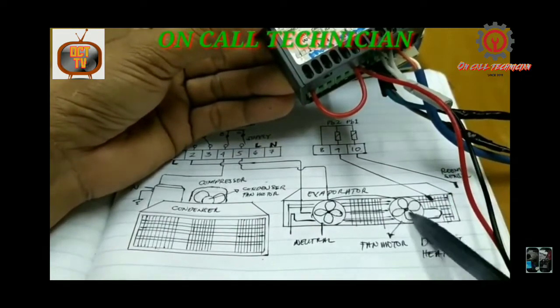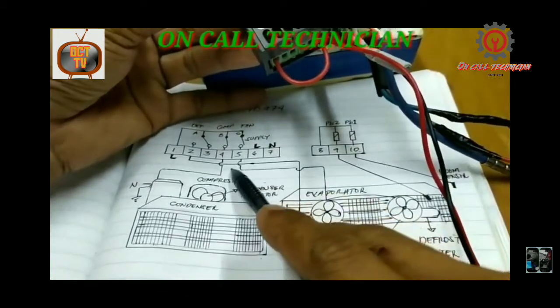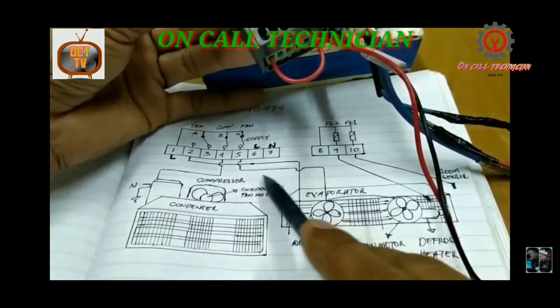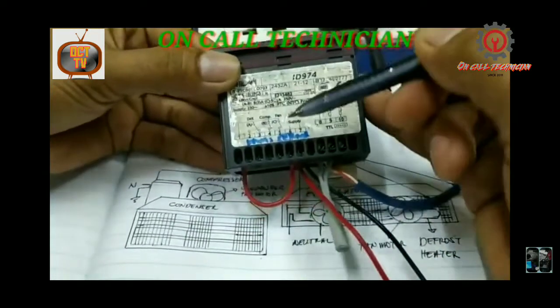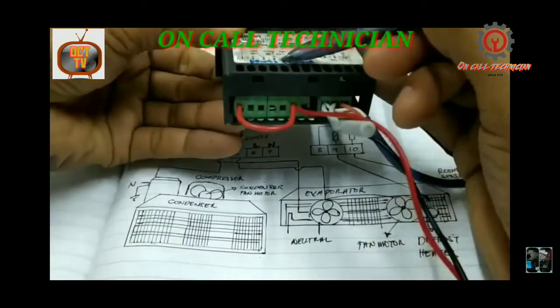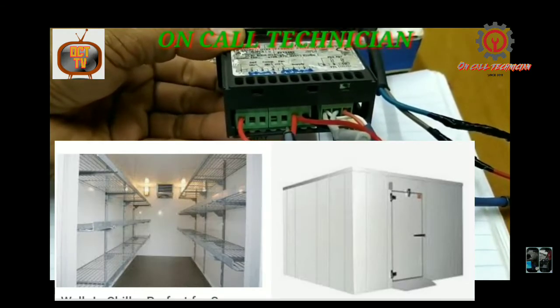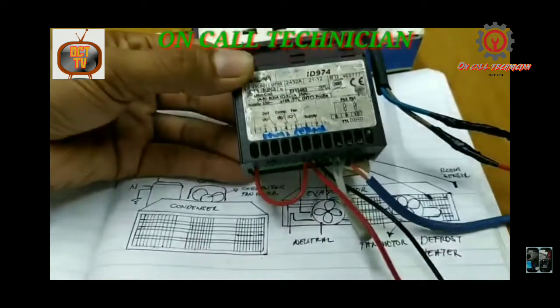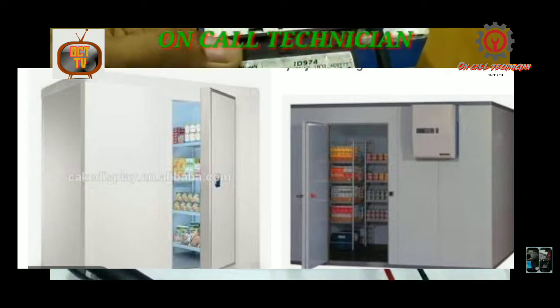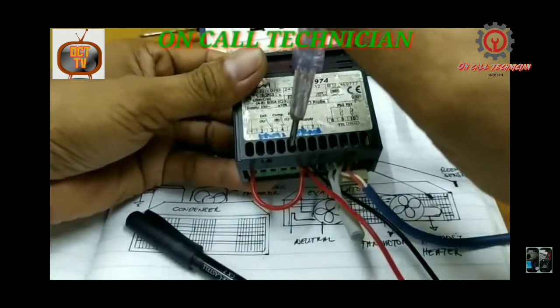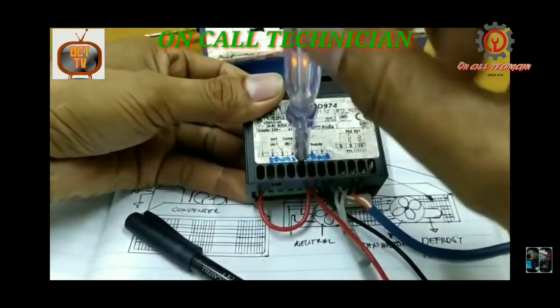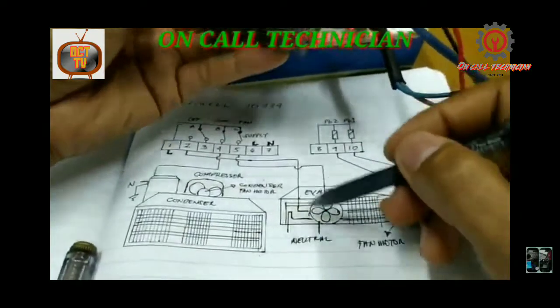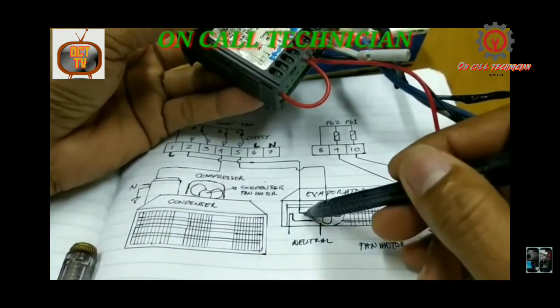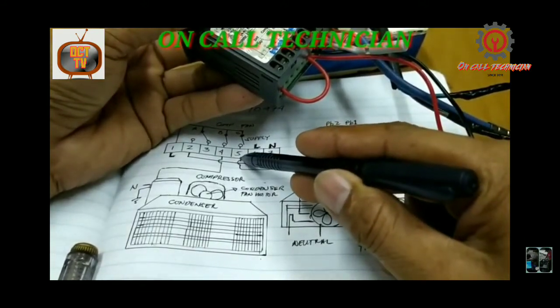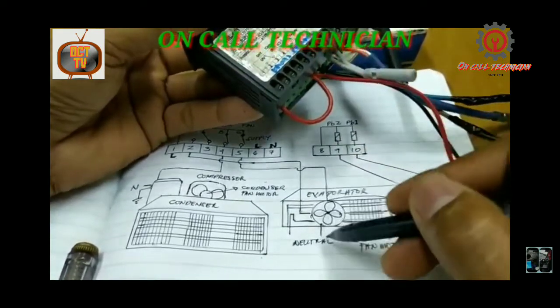This is the evaporator fan motor, guys. So the live, which is connected in series of the 2, is connected to terminal number 4. No, terminal number 5, sorry. Terminal number 5 is the fan motor. If you use that also, guys, in a cold room, on the freezer, walk-in chiller and freezer, once again just use a contactor with overload. Here it is. Terminal number 5 is lit up, which means it's on. So if you put a fan motor on it, it will spin. So here are the connections, guys. So it is wired in series and goes to terminal number 5.